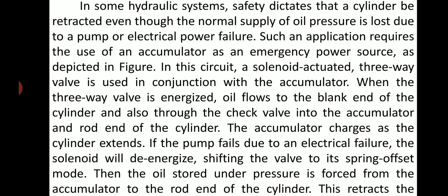When the three-way valve is energized, oil flows to the blank end of the cylinder and also through the check valve into the accumulator and rod end of the cylinder. The accumulator charges as the cylinder extends. If the pump fails due to an electrical failure, the solenoid will de-energize, shifting the valve to its spring offset mode. Then the oil stored under pressure is forced from the accumulator to the rod end of the cylinder.